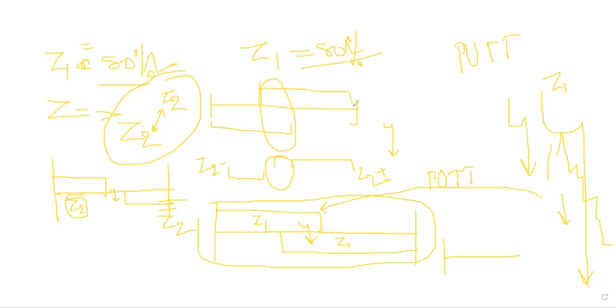But what is the real condition of the fault? You are saying you put some line. What is the percentage of the fault for the A breaker, and what is the percentage for the B breaker? What is the real fault? Maybe due to insulator damage with a high arc, the real fault would be zone 1, maybe more than 80%, for the A breaker, and for the B breaker maybe 40 to 60%. This is the real fault condition you are describing.